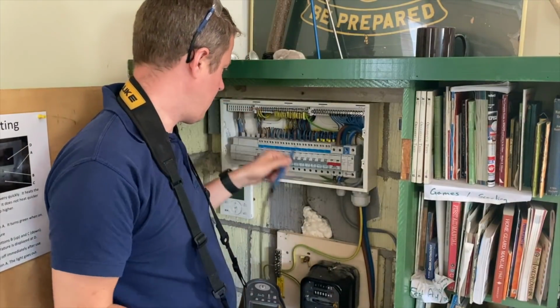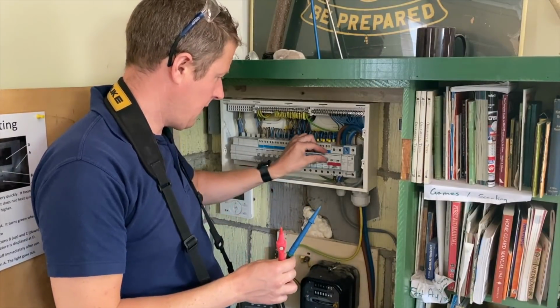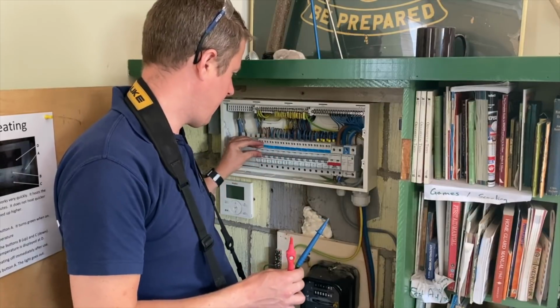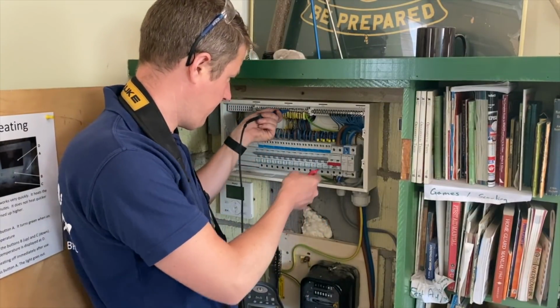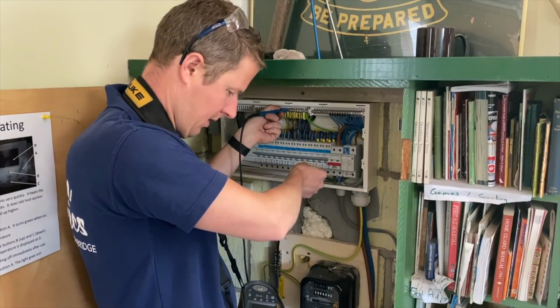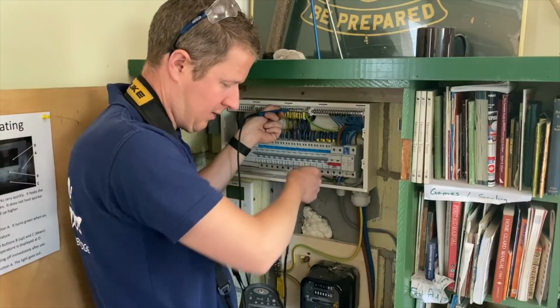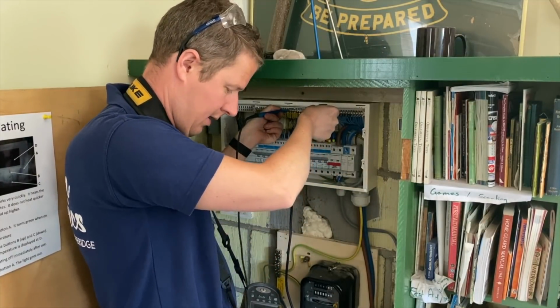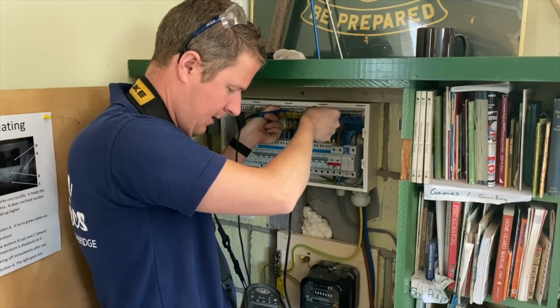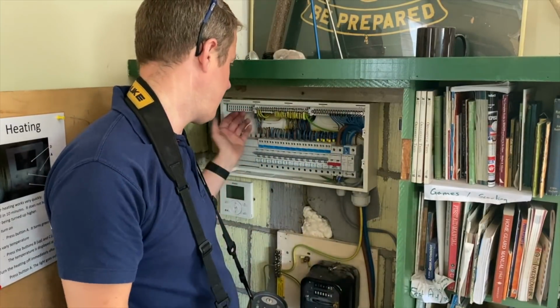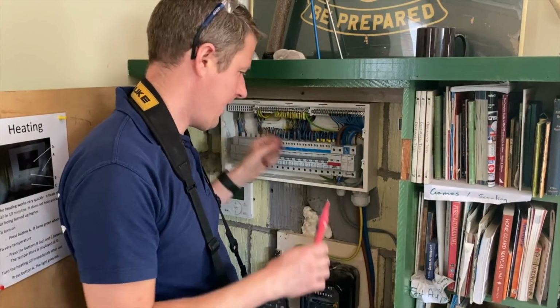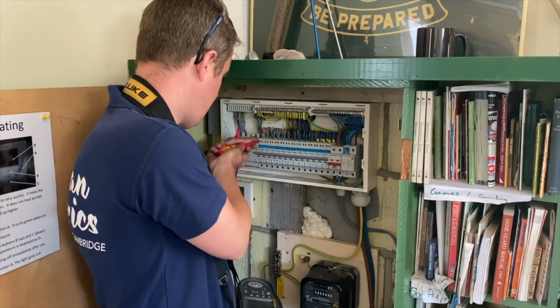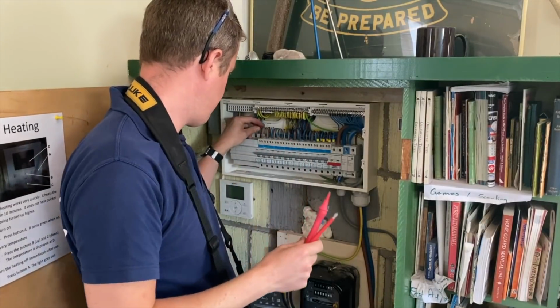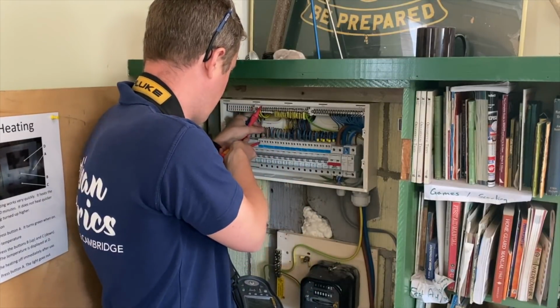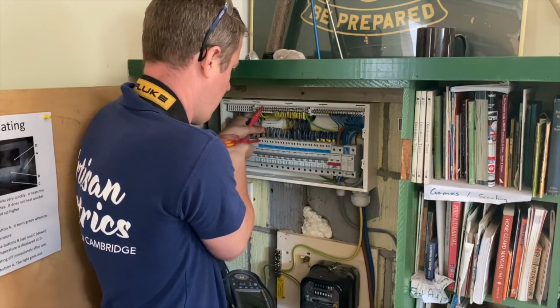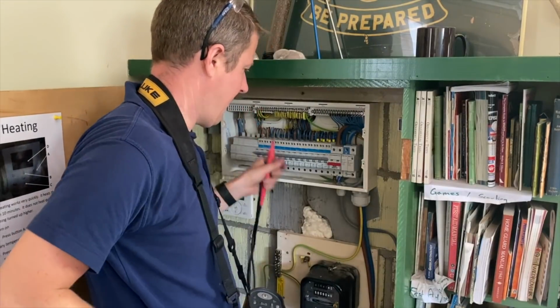Now what you can actually do, in fact maybe we can just do this for fun, you can test through all the circuits if you want to. So if you just test from the bus bar, see I've got 20 megohms, so I know that actually everything's fine, and I can do the same with this, neutral to CPC, 29 megohms, so I know that actually everything's fine. If say for example one circuit was shorting out, how would I do that? No, I can't actually do it that way. But if any one circuit had a low reading, it would bring the readings of the whole lot down. So that's actually quite a quick way to do it.